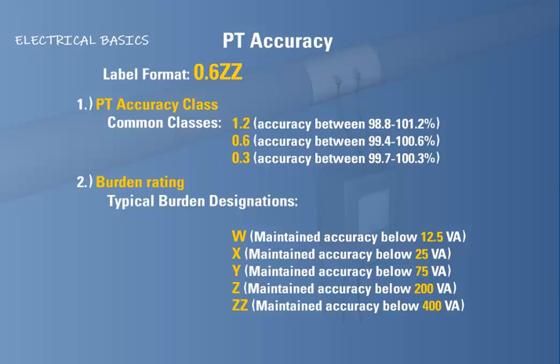In this example, the PT rated 0.6 ZZ would have an accuracy between 99.4 and 100.6%, as long as the burden of the PT remains under 400 volt amperes.